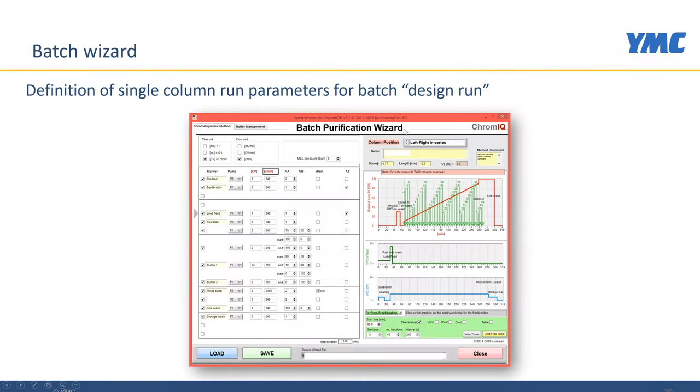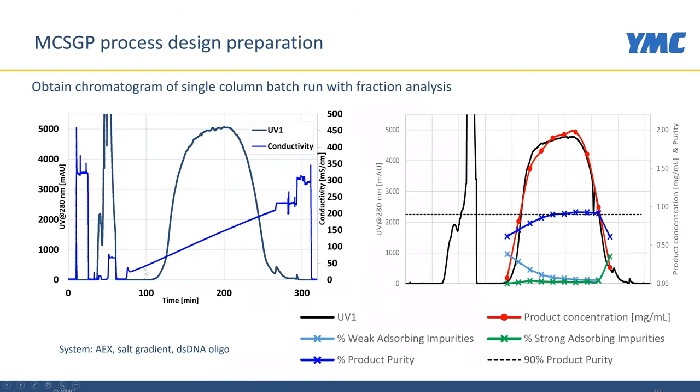The batch design run is created using a batch purification wizard included in the ChromIQ software. It can run linear gradients and perform fractionation. This is the result from such a design run: we have a linear gradient, UV signal, fractions that have been taken and analyzed, yielding a purity profile and product concentration. We can see impurities in the front and in the back, meaning we will need to purify the main product in a center cut purification. This was an anion exchange salt gradient run on double-stranded DNA oligo.